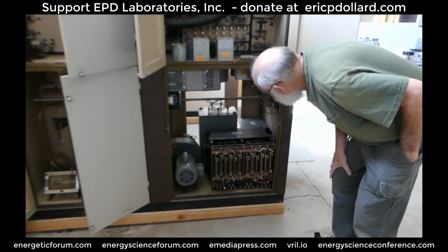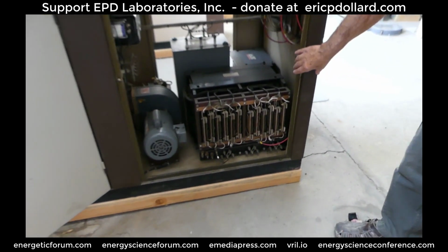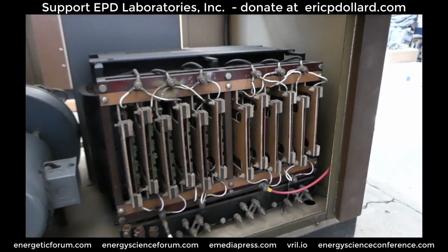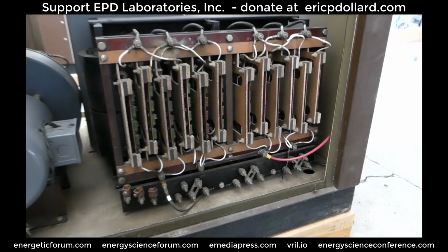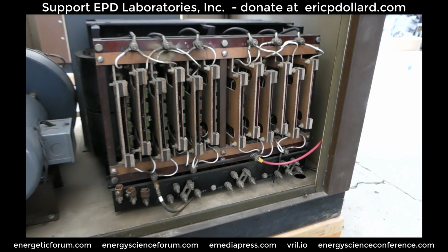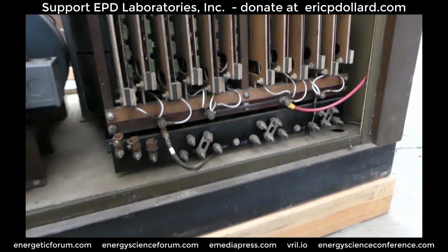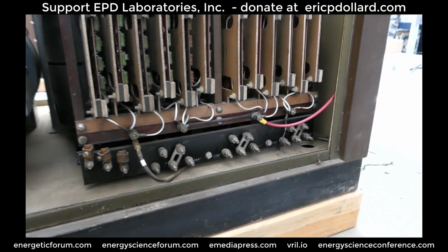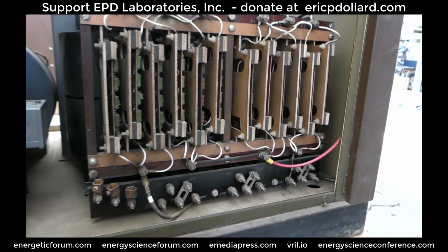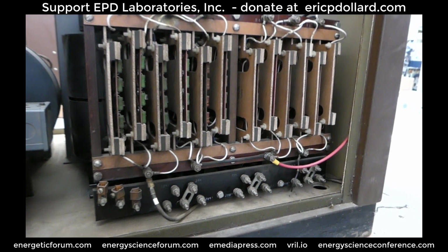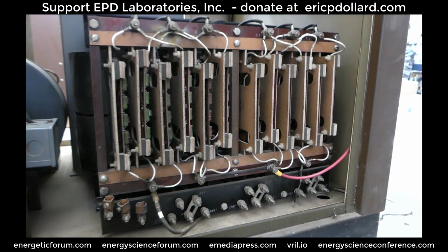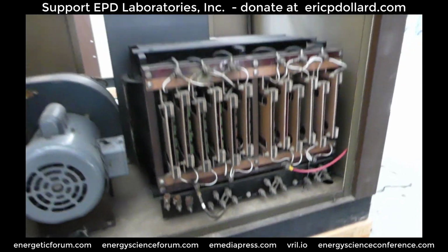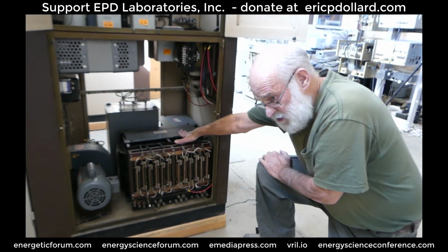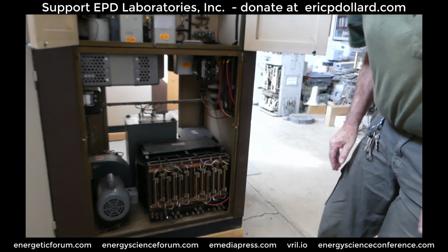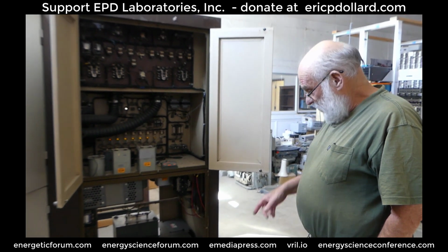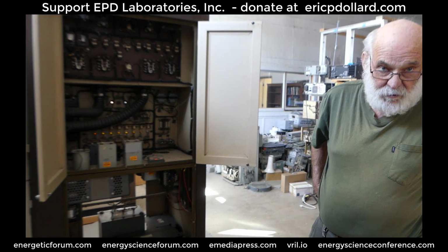Now there's some problems here that are going to have to be addressed later down the line. This is not really a good design here, the power coming in is too close to the high voltage, it's unacceptable clearance. So if something gets in there and that flashes over, then the high voltage side of this will backfeed into the low voltage power line, and that can cause a lot of complications with other things running on the same power. So I think my plan, because these things are in a fixed location, is to completely remove this, change all this around, and in the power supply panel, that's where these will be, and then just send the high voltage straight over here.